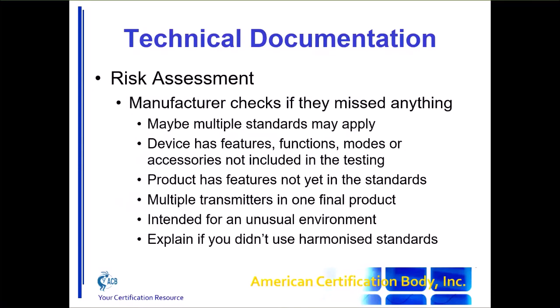The risk assessment, a lot of people have problems with. I've seen risk assessments that were half a page long, and I've seen risk assessments that were 50 pages long. I think probably the best solution lies somewhere between those two points. But in general, it's checking which standards apply. Have you got all the standards that apply, not just the first one you came to? Has the device been fully assessed, or has it got functions that aren't covered by the standards?